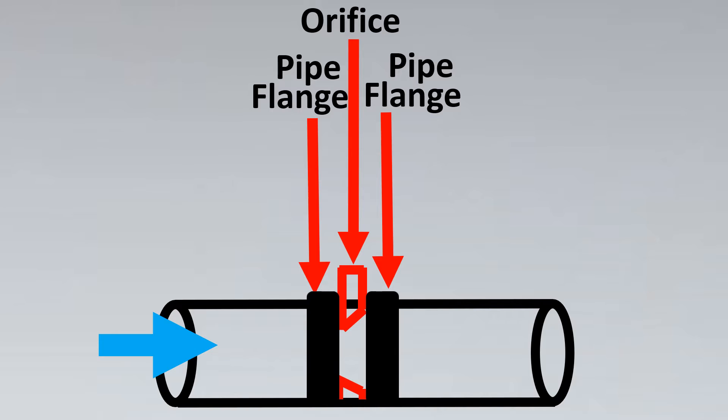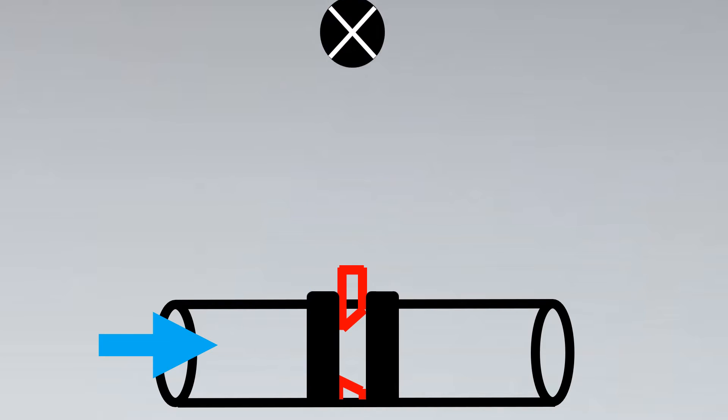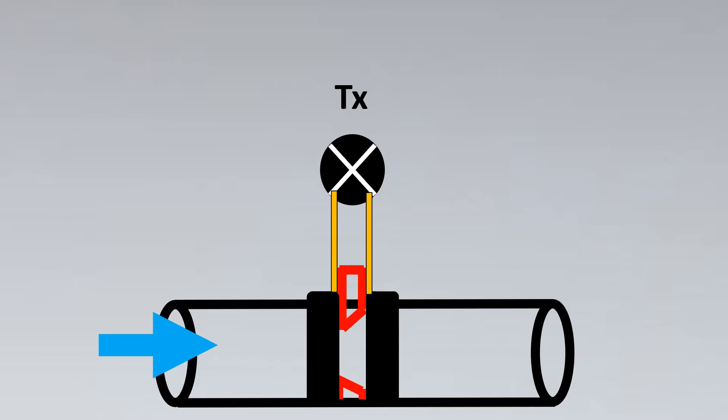Now we look into the type of tappings that are available in the orifice and which tapping has to be used when. So for example we have our transmitter here and when the tapping is taken one at upstream side and one at downstream side, if it's very near to the orifice plate then this type of tapping is termed as corner tapping.